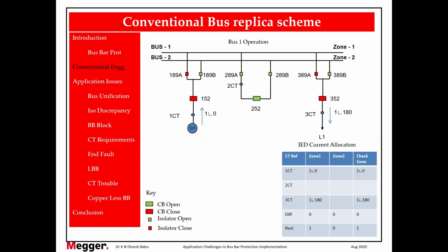So if it is confusing, just understand it with a simple thumb rule. If the current is flowing in the same direction where the CT neutral point is earthed, then it would be 0. If the current flow is opposite to the star point earthing, it would be 180. So in this example, 1 CT is earthed towards the bus bar, 3 CT is earthed towards the bus bar. In fact, if you have 20 CTs or 40 CTs in your substation, all CTs are earthed towards the bus bar. So whenever current flows towards the bus, the angle is 0. Whenever the current is flowing away from the bus, the angle is 180. Simple. So this logic is very clear.